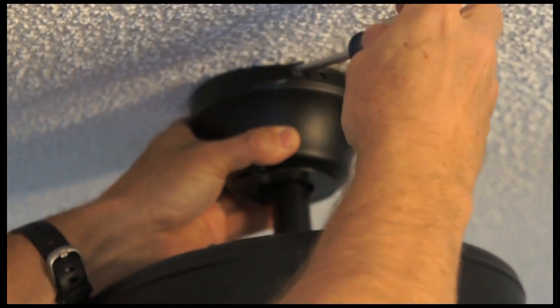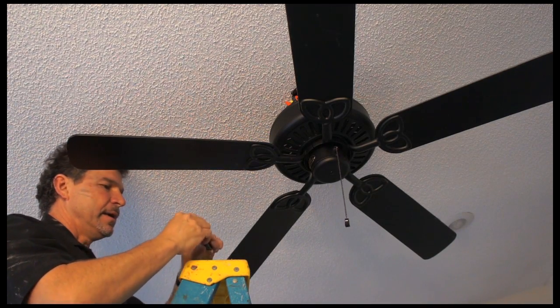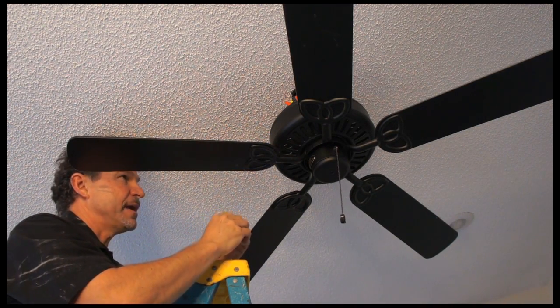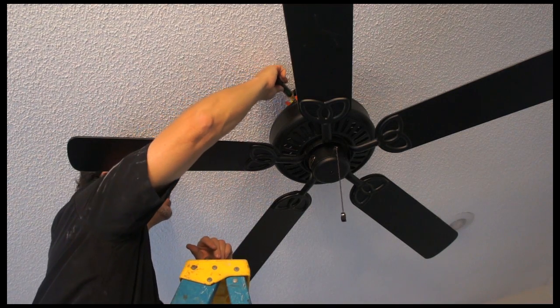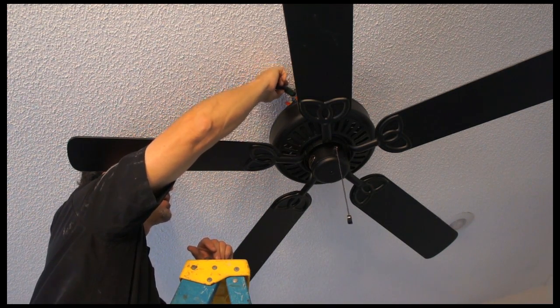I'm going to remove the canopy to expose the wires, and I've already turned off the switch that controls this fan, but I'm going to check it with my tester. And I can see that the circuit is dead.